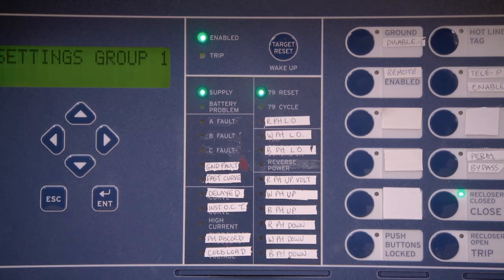Delayed curve indicator. This will illuminate while in a slow curve tripping sequence. These controls can be programmed from 1 to 4 operations until lockout. Typical in distribution is 4 shots till lockout. Instantaneous overcurrent. This light will indicate upon tripping on instantaneous overcurrent. This setting would be typically set for 1 shot till lockout. This feature is usually not set for these controls.